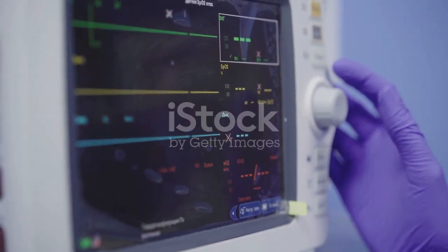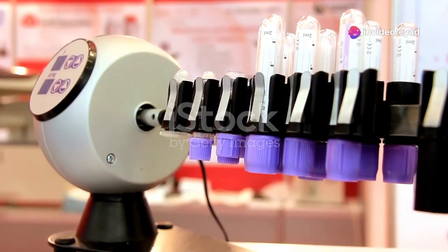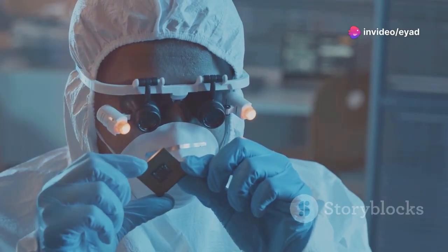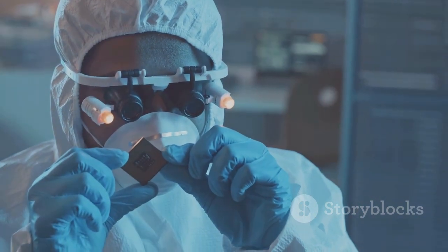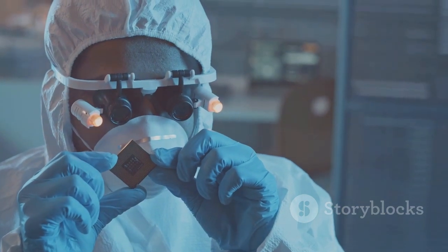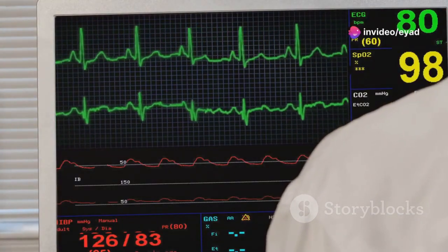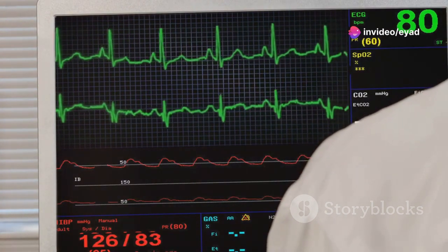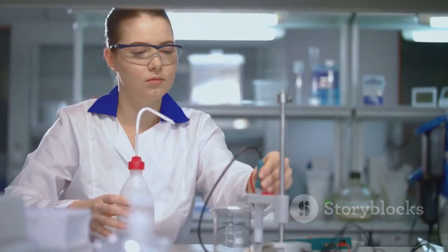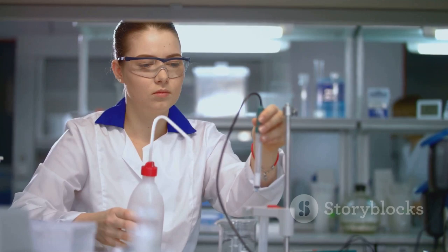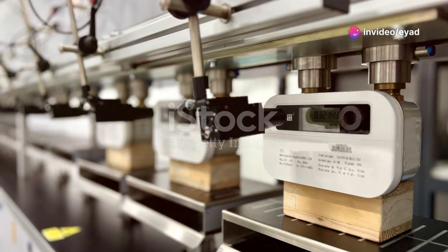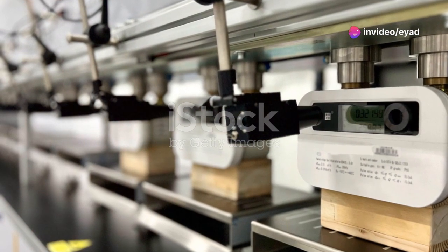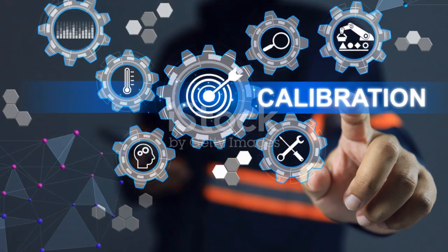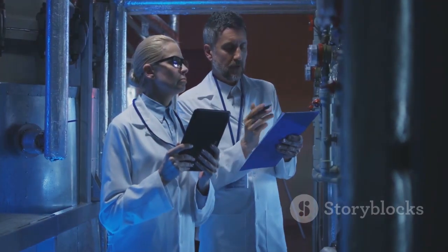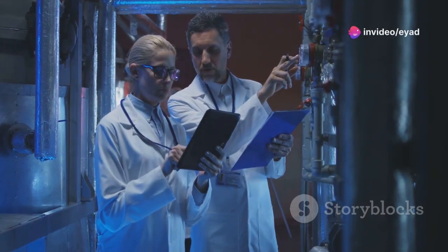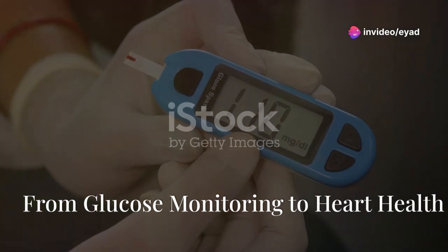Sensor drift. The case for regular recalibration. Biomedical sensors are not immune to the passage of time. Like any other instrument, they can experience wear and tear, environmental exposure, and other factors that can cause their performance to drift over time. This means that the relationship between the sensor's output and the biological parameter it's measuring can change, leading to inaccurate readings. Regular recalibration is essential to combat sensor drift and maintain the accuracy of biomedical sensors. Recalibration involves repeating the calibration process at regular intervals using fresh standards to adjust for any changes in the sensor's response. The frequency of recalibration depends on the specific sensor, its intended use, and the manufacturer's recommendations.